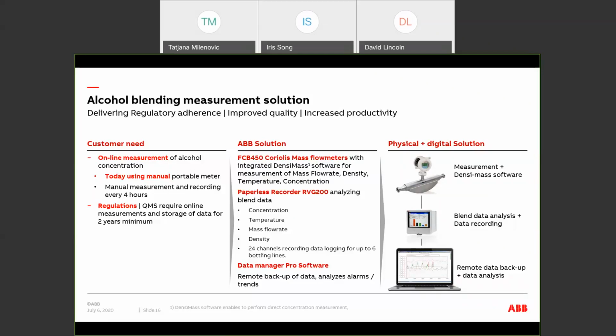In a recent audit, they'd been asked if they could shift to automated online measurement of alcohol, so they came to us to ask how they could do that. What we identified is that within one of our smart devices, our Coriolis mass flow meter, there's already a DensiMass software algorithm that could be enabled to take the measurements of concentration. So that was a tick - we have a device that will measure exactly what they're after.